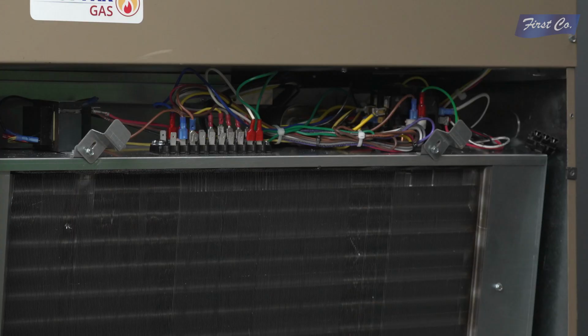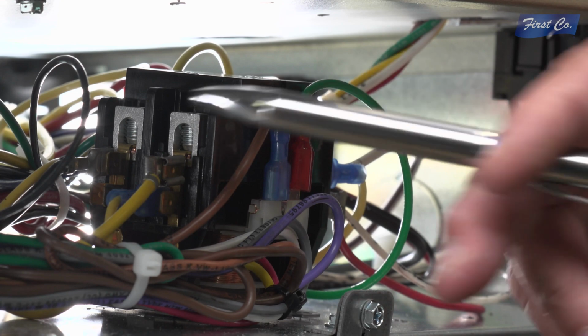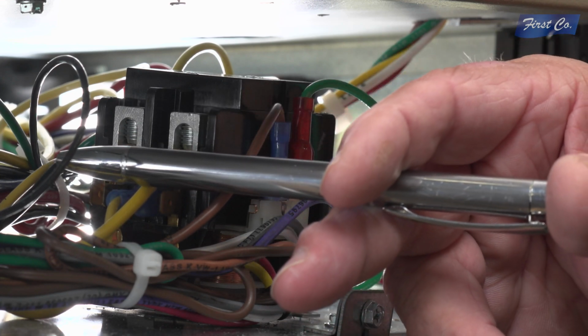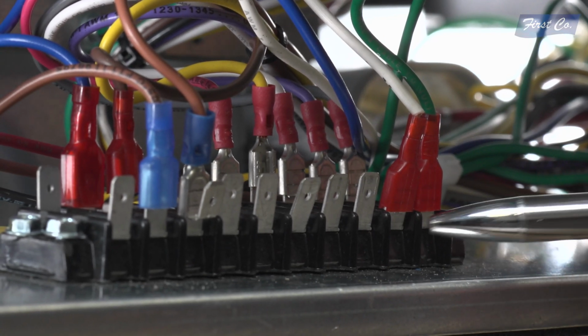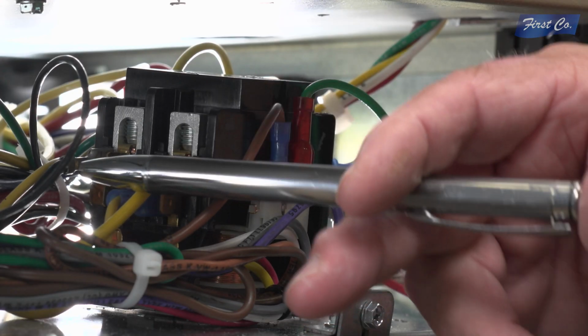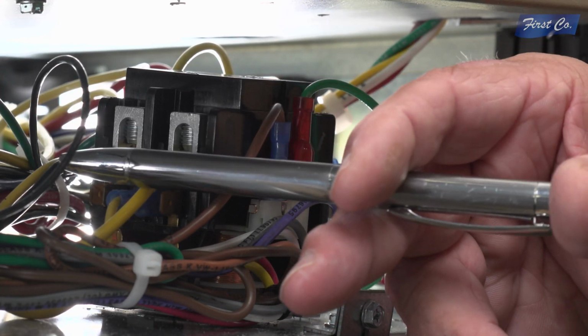Once you remove the top access panel, if there's any problems or you can't get to any of the parts, the whole heating section can be loosened and pulled out and serviced on your bench. Within the control section, all your components are front and center for easy diagnosing. You can gain access to the contactor and the transformer. There's a board in there for the heating control section that lets you control the heating fan motor without gaining access to the interior of the unit. It has the run capacitors front and center, so everything a service personnel has to do is right here, front and center, with easy access.